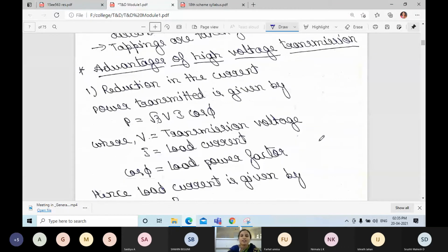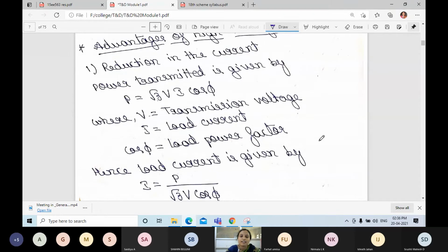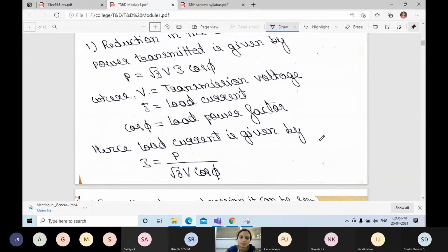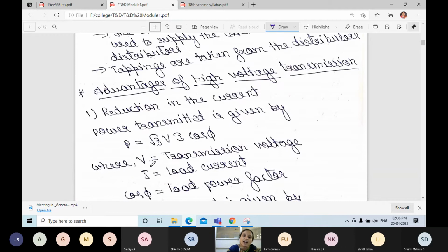Next, we shall know about the advantages of high voltage transmission. First, reduction in the current. How will we reduce the current? Power transmitted is given by the equation P is equal to square root of 3 VI cos phi, where V is the transmission voltage, I is the load current, and cos phi is the power factor. I is equal to P divided by square root of 3 into V into cos phi. As you increase the voltage level, you can observe it is inversely proportional, so the current will be reduced.